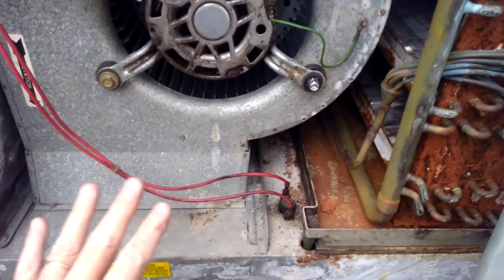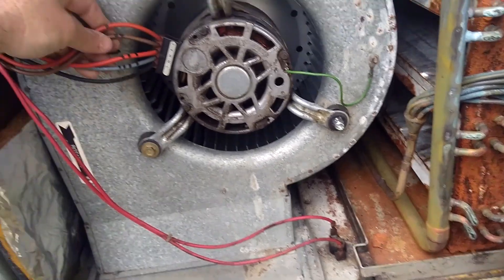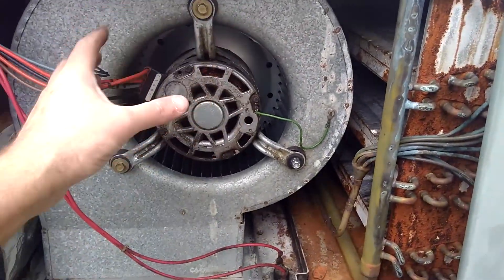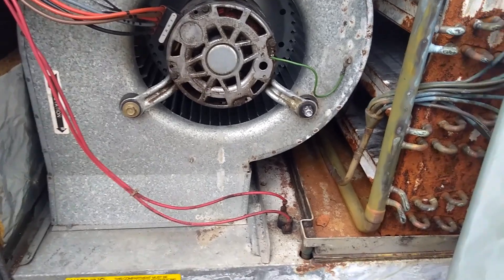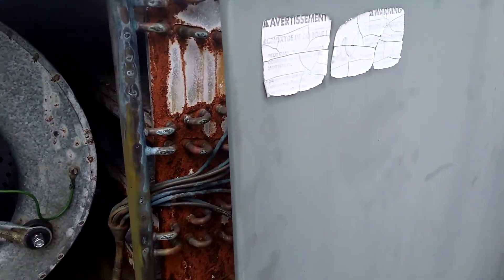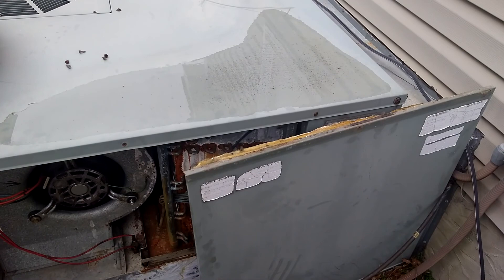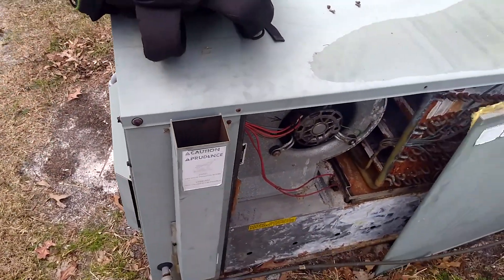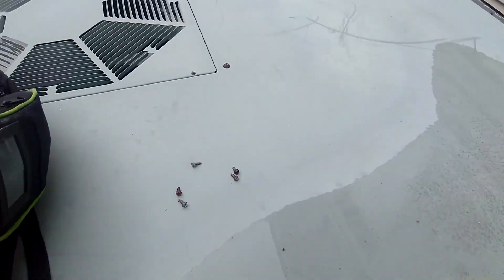We got the motor and assembly back in. You just take one panel off, open up and disconnect these limit switches, disconnect the wires — which I've got marked one through five — take out this screw and this screw, and the whole thing just slides out. I wish they still made them that way. This coil might be springing a leak before long; I think this is the last winter they're going to have the unit. I've changed the heat exchanger and the burners twice over the many years I've worked on this.